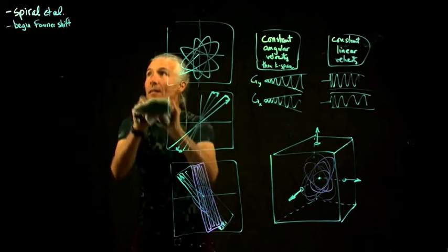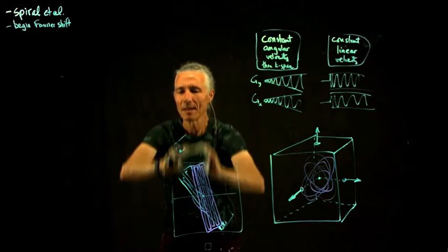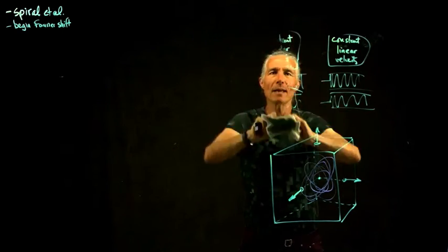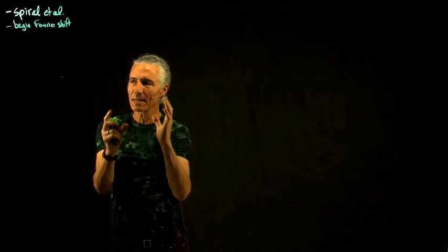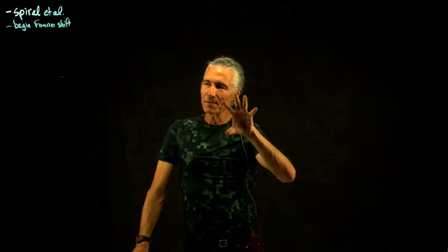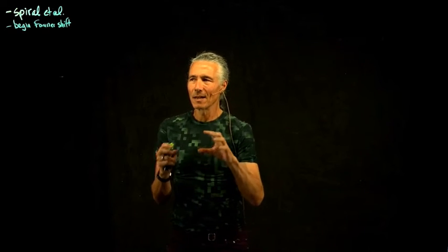Next time, when we talk about the Fourier shift theorem and B0 defects, we'll see that the effect of a B0 distortion for a standard rectilinear echoplanar scan is just to cause a spatial shift. So B0 defects cause spatial shifts. The image looks sharp, but it gets distorted. What happens in spiral is that a B0 defect causes blurring. The image is geometrically accurate, but blurred. And in some respects, it's better because it doesn't distort things. It just blurs them a little bit.